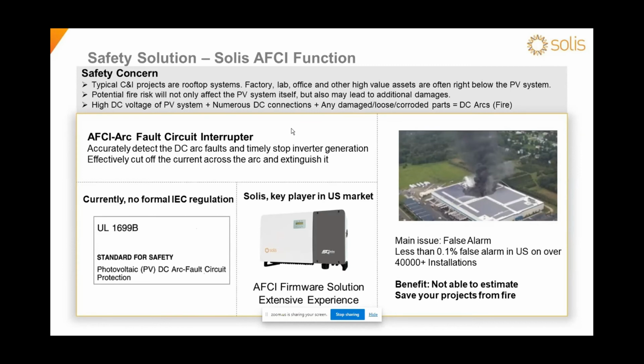So we add this arc fault circuit interrupter inside the inverter. This function can detect the DC arc very precisely and timely, and then stop the inverter, cutting it off from the system so that fire will not happen. This function also passes UL certification.